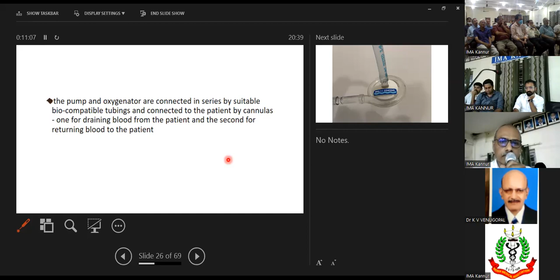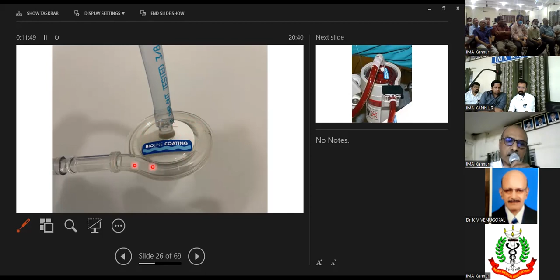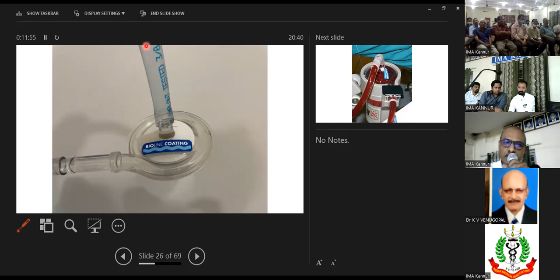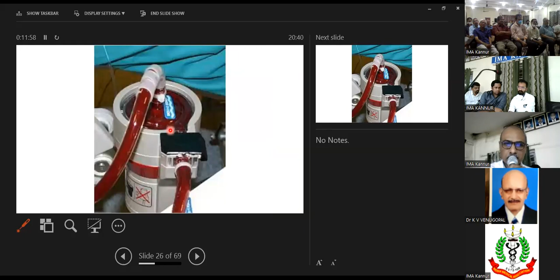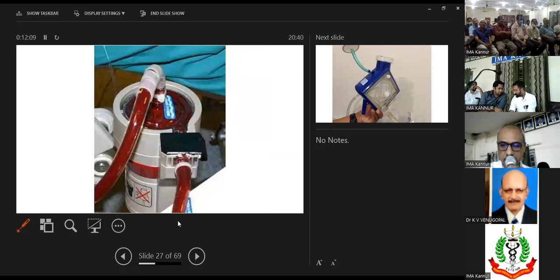This is one of the pump heads, which actually is a polymer sort of a cone inside which there is a component which is line free, which is rotatable. This one works without any direct contact. It works on magnetic induction principles. And as this white disc inside rotates, it keeps pushing the blood out with the centrifugal force which is generated, and blood comes through this tubing and goes back to the patient. Blood from the patient comes through this tubing into the pump. You see here one of the Maquet pump heads inside the machine. The blood from the patient is coming here, and then through this, it is going back to the patient.